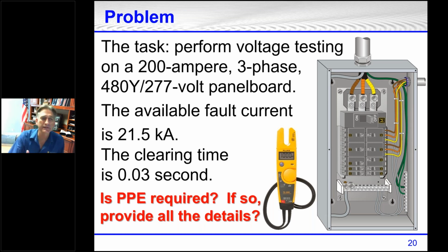So, okay, I'm giving you a task. You're going to perform voltage testing. That means the panel board is going to be energized. I'm giving you the available fault current is 21.5 kA, 21,500 amps. The clearing time is 0.03 second. And then I have a question: is PPE required?